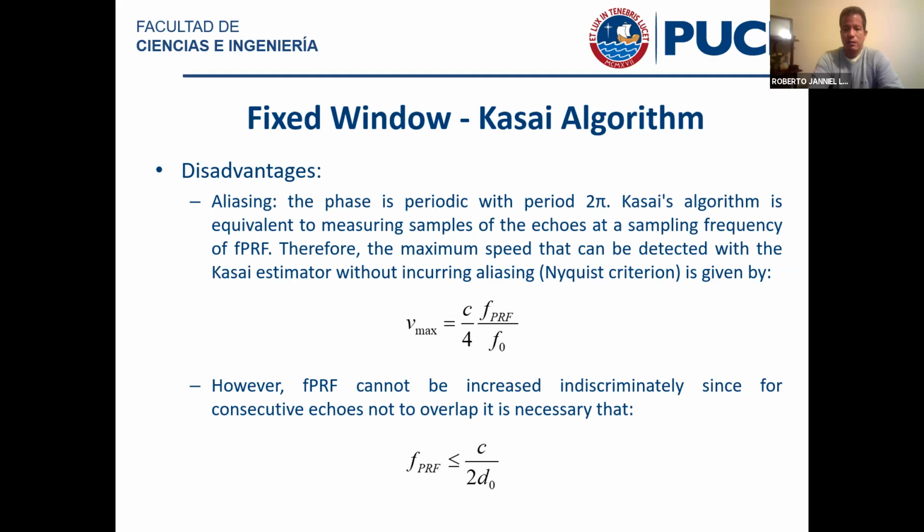You can directly estimate it, and it will tell you exactly, as a function of the depth that you want to analyze, the center frequency of the transducer, and the sound speed. That's it, period. That's as fast as you could do it. And you will see that in practice, the PRF is limited to be in the kilohertz range. If you put in numbers that are typical, you will see that it's in the kilohertz range. That tells you that there will always be the potential for aliasing, because unfortunately, physics tells you that you cannot fire a transducer magically fast. Simply cannot.